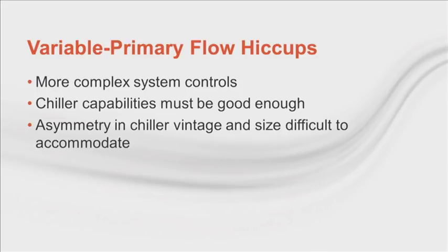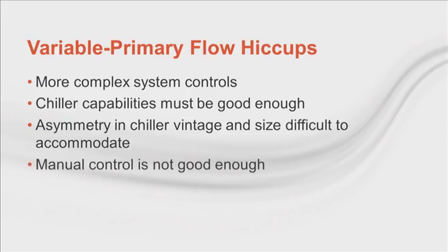Modern system controls can accommodate VPF, but manual plant control is difficult. A minimum flow bypass must be installed in most applications to keep the chillers online during low load periods when the system flow is below the chiller's minimum. Having said all that, we still see this as a popular configuration choice for new systems especially, because the first cost and operating costs are so attractive. We've been doing variable primary flow long enough now that we have seen a lot of people using it when it's not ideal. Small systems have challenges with VPF.